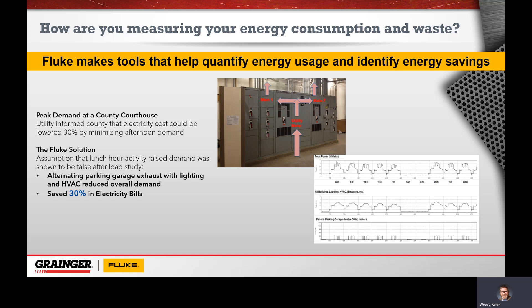Not only did they reduce their electricity usage, they were also able to shave off that peak demand, and it ended up saving them 30 percent in their electricity bills going forward. You can see a graph here with little spikes at the bottom — those are the fans — and then the overall use in the offices. Those little spikes on top of that base demand is what put them over the top on peak demand. Really, it's about figuring out not so much what you're using, but when you're using it, to lower the overall demand curve to the utility.